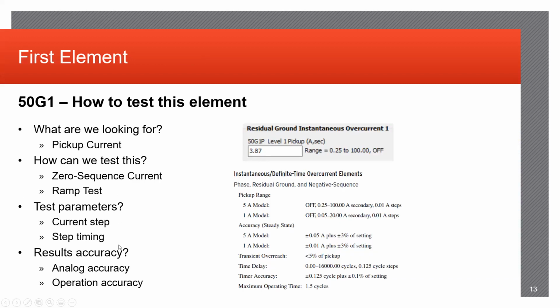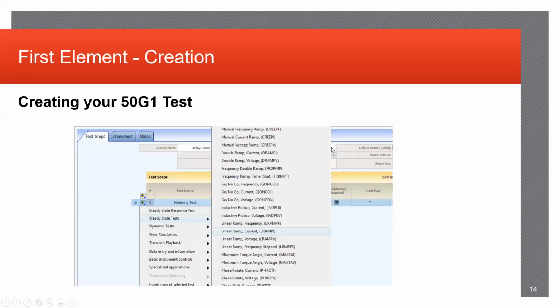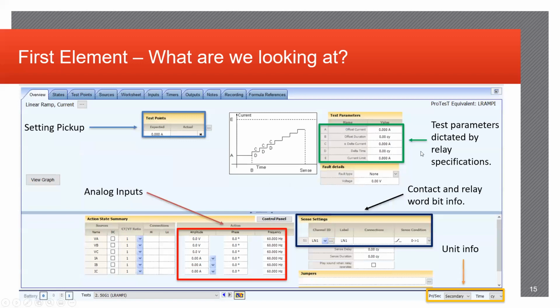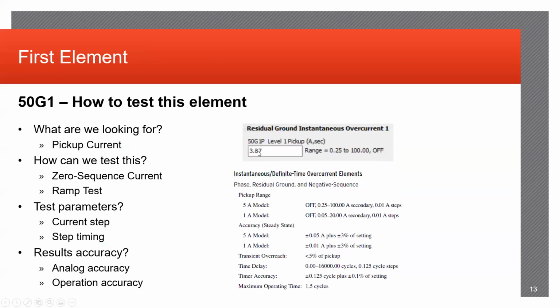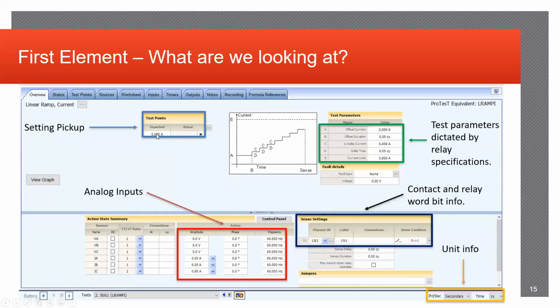So, setting up your test parameters, we'll go right into it. Actually, it shows in this next slide. So, identifying the tests that you're going to be running, for this 50G1, in this case, we're going to be using linear ramp current, and this will bring you into your settings. Shown here in the top left corner in the blue box is going to be your expected test point. As shown in the previous slide, your expected test point for this 50G1 element is going to be 3.87. This is what you'd be utilizing here. This is what the test set should be reading when you're testing the element, and it will be shown in your results as well.